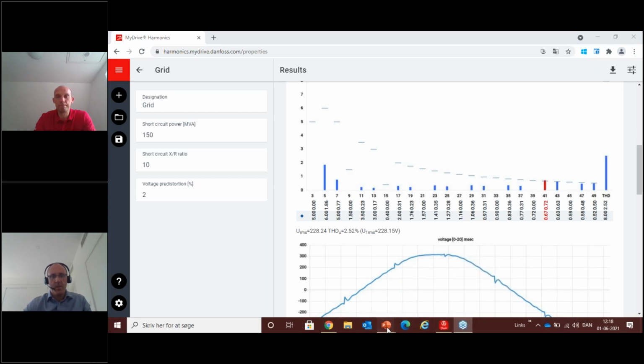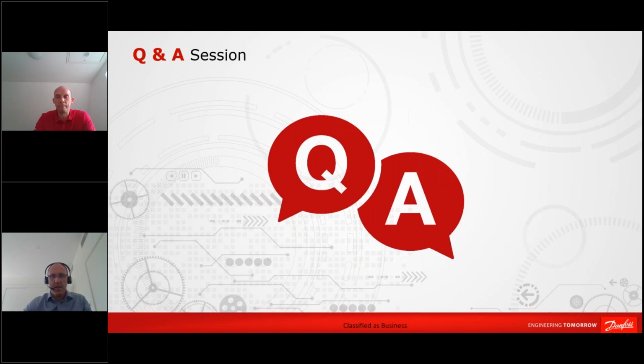Yep, very good. Then we have a question related to the higher order harmonics with the active front end, so the 2 to 150 kilohertz range. Is this also an issue with active and passive filters? It's also an issue with active filters. No matter what you have of active in-feed converters, they are having switching frequencies, and when they're switching towards the grid, you will see higher order harmonics being generated.